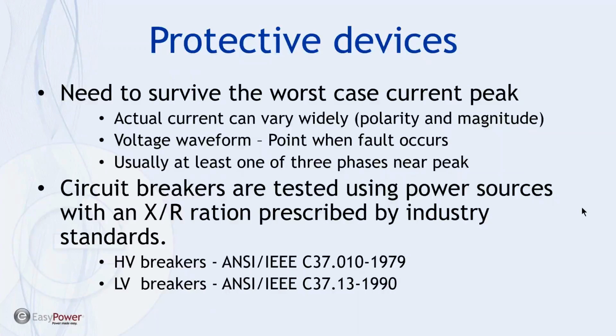So circuit breakers are tested using power sources with an X over R ratio as prescribed by industry standards. So there could be variation, and again, there's a need to have everybody on the same page. So for the high voltage breakers, we see ANSI standard IEEE C37.10, and for low voltage breakers, it's C37.13.